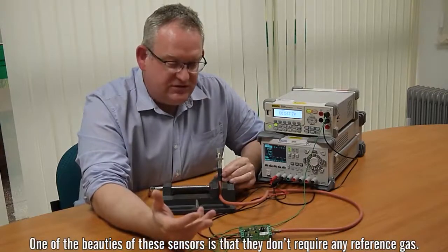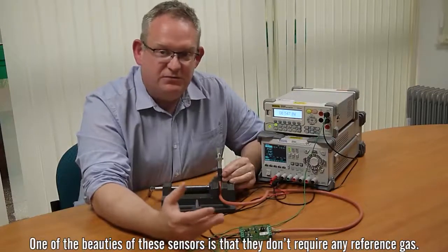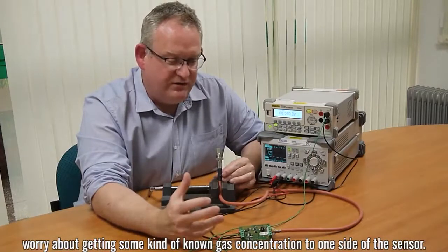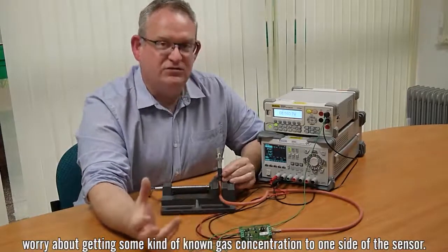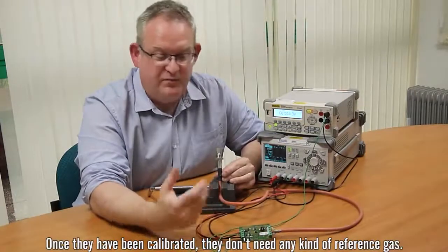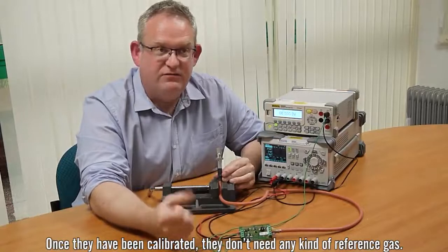One of the beauties of these sensors is that they don't require any reference gas, many other sensors do require reference gas and that means you have to worry about getting some kind of known gas concentration to one side of the sensor. That's not the case with our sensors, once they've been calibrated they don't need any kind of reference gas.